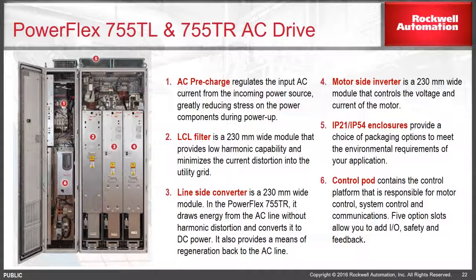The line-side converter is a 230 millimeter wide module in the PowerFlex 755TR. It draws energy from the AC line without harmonic distortion and converts it to DC power. It also provides a means of regeneration back to the AC line. Motor side inverter is a 230 millimeter wide module that controls the voltage and current to the motor. The enclosures, IP21 and IP54, provide a choice of packaging options to meet the environmental requirements of your application. There's a control pod that contains a control platform that's responsible for motor control, system control, and communication. 5 option slots allow you to add I/O, safety, and feedback.